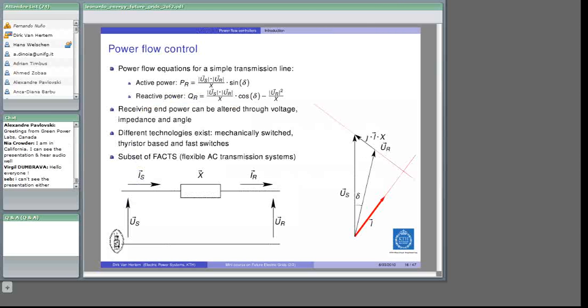How does it work technically? Again, I won't go too much into detail, but the very basic equation for the power flow through a simple transmission line is shown here. The active power flow is the product of the amplitude of the voltages at the sending and receiving ends, divided by the impedance, and multiplied by the sine of the angle between the two voltages at sending and receiving side. Below is a simple network, and on the right hand side is the phasor diagram.